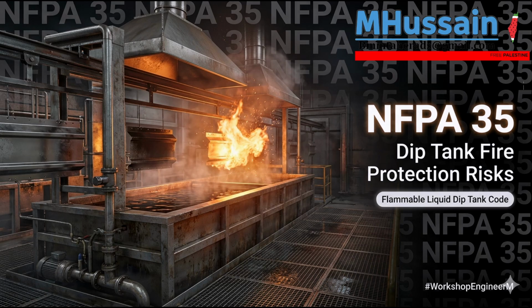Now let's talk about holding the heavy equipment up. Structural supports. Yeah, if you have a 5,000-gallon mix tank on the second floor, it is being supported by heavy structural steel columns. The code demands that load-bearing supports for vessels be protected. But if a fire breaks out, I mean, steel seems tough, but it really isn't, is it? Not under thermal stress, no. Structural steel is incredibly strong at room temperature, but it is highly susceptible to heat. How susceptible? At roughly 1,000 degrees Fahrenheit.